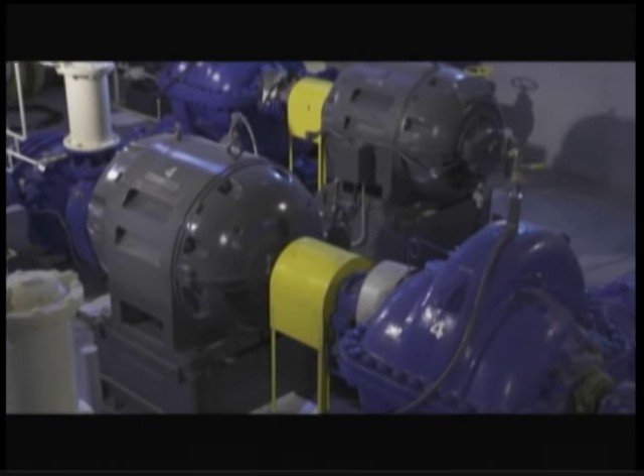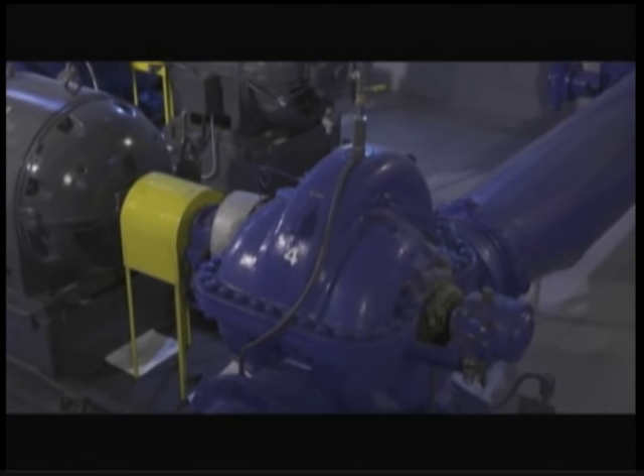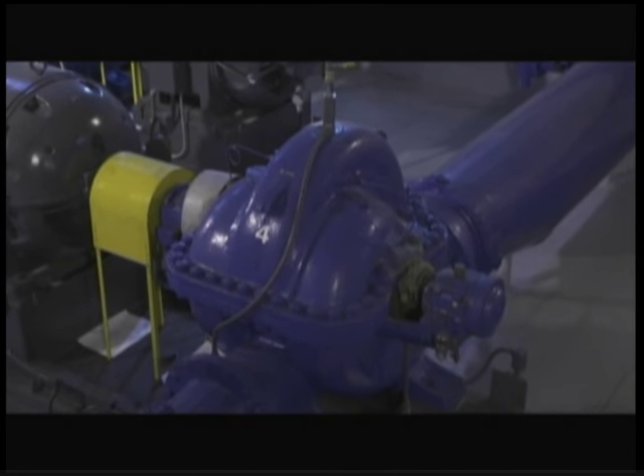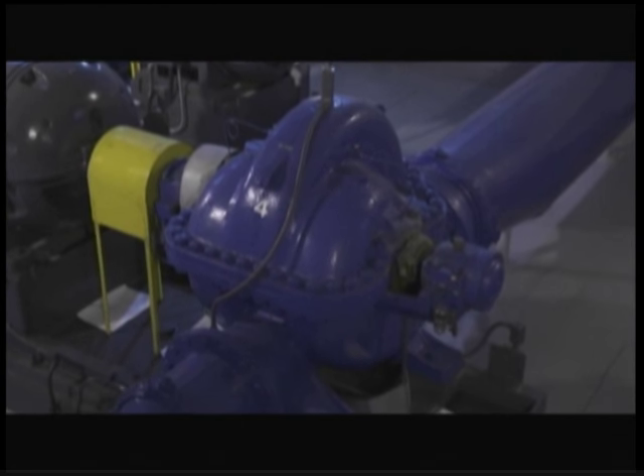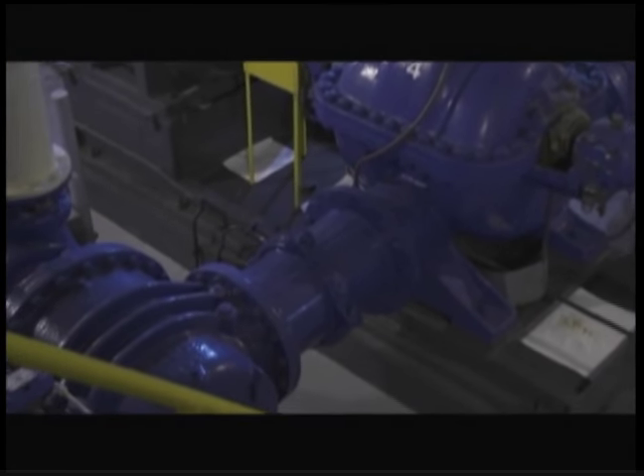The term 'horizontal' does not indicate the position of the pump, but rather the orientation of the shaft centerline. The volute, or casing, is split into two halves — the top and bottom — along the centerline of the pump shaft.